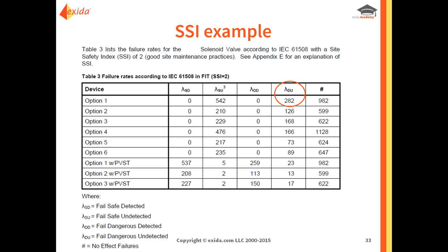Wow, look at the difference here. If that site goes to an SSI 4 and they have all the procedures in place, it's drastically reduced. Now you have your DUs at 142, and your SUs at 325. So if you didn't catch the differences there, at an SSI 2 compared to an SSI 4, you can do your own calculations, which will be in exSILentia as well. Look at the difference here, almost a 50% reduction in failure rates for dangerous undetected from an SSI 2 to an SSI 4.